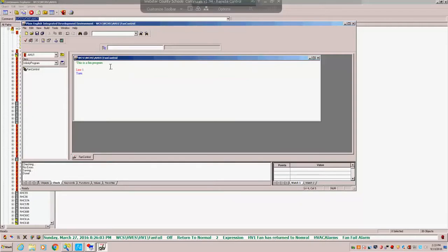First thing you want to do is, if you're working with outputs, you turn it to whatever state you want these things to start in. We want the fans to be off. Okay. So whenever I start this program, it's always going to come up here to line 1 and turn the fan off. Whatever it does after that, it's going to be deciding what the exit conditions are. I'll put some lines here in a minute that will say when these lines are true, do something else.